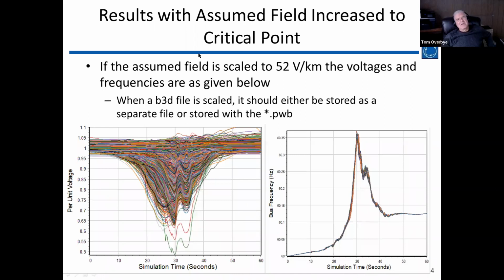What I typically like to do is scale an event up to a critical point, where I lose a solution. In this case, I went up to 52 volts per kilometer. These are my voltages. If you know voltages from a power system point of view, you know that as values drop below 0.8 and 0.7, you're stressing the grid, and this was clearly a stressed grid. If I tried to go above 52 volts per kilometer, the system did not solve.